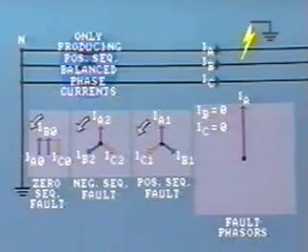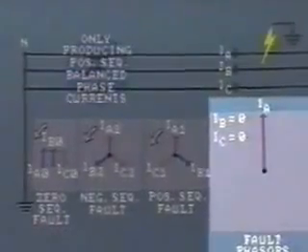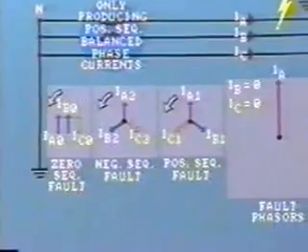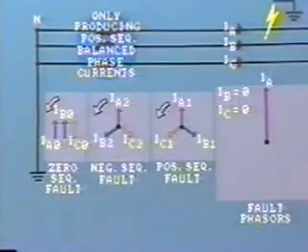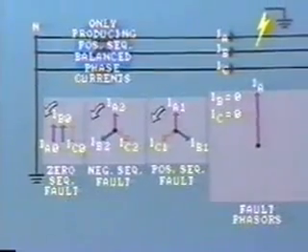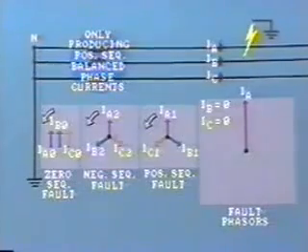This is what we should expect. There is a heavy flow of current in the grounded line, but there is zero current flowing in the uninvolved phases — remembering that we are assuming load to be zero. Again we have seen that the sum of the positive, negative, and zero sequence components for each phase add up to give us the actual fault values. So we now come to another very important conclusion: where a ground fault exists, all three sets of symmetrical components are present — that is, positive sequence components, negative sequence components, and zero sequence components. And within each set of components, the voltages and currents are of equal magnitude.